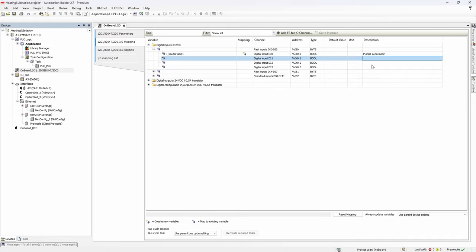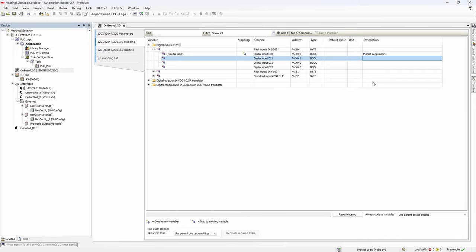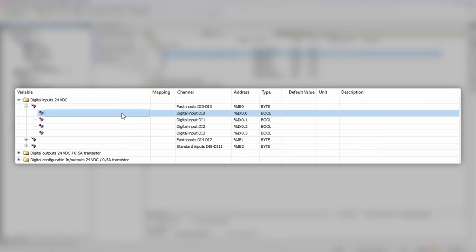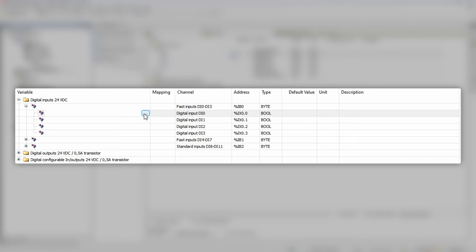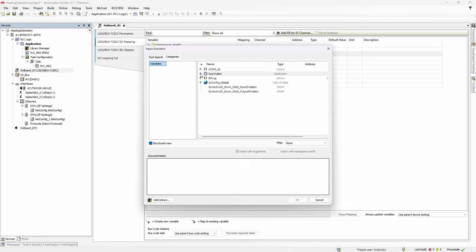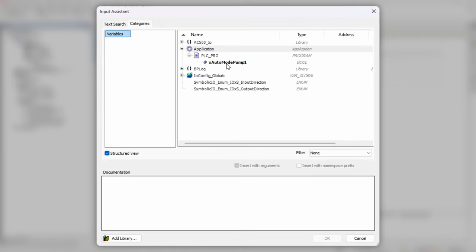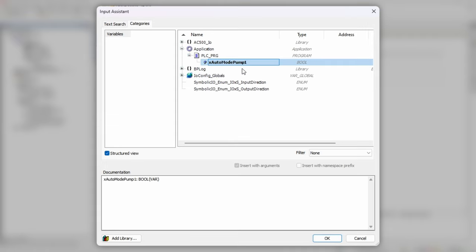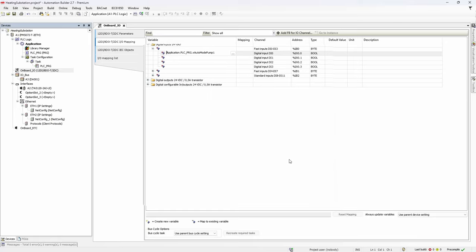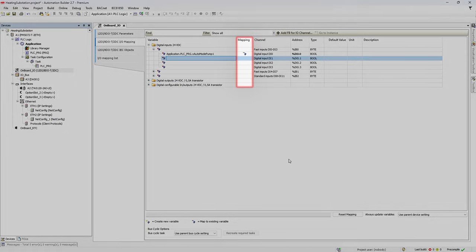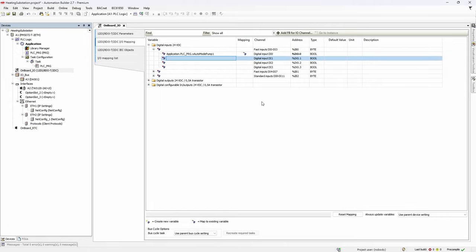The second method allows you to attach already existing variable in the project to the specific IO channel. You can imagine this could be useful if you start developing control application without electrical drawings ready. Then you can proceed with project development and do IO mapping on a later stage. The same way you double click variable field of the input di0, but this time instead of typing the name, click this three dots button and locate desired variable inside the project. Click OK, hit enter, and get the result. You may have noticed that the icon in the mapping column has changed and now reflects the second mapping type.